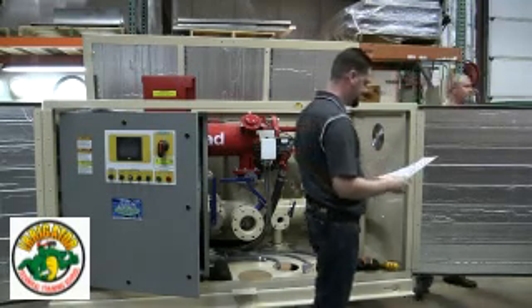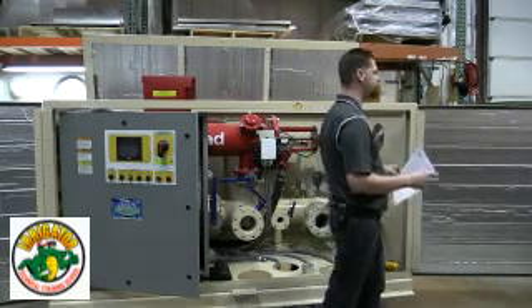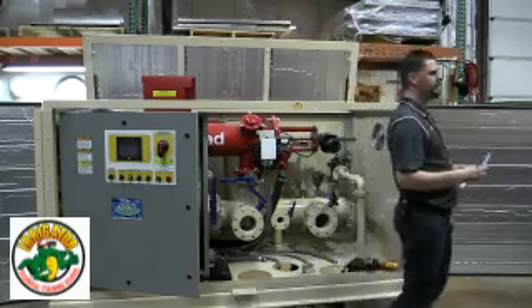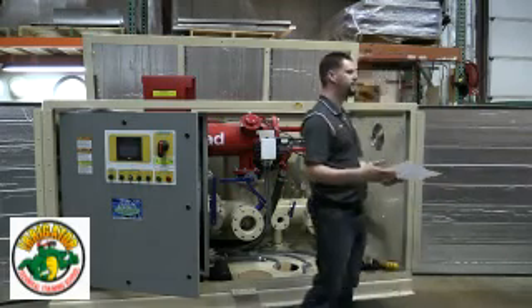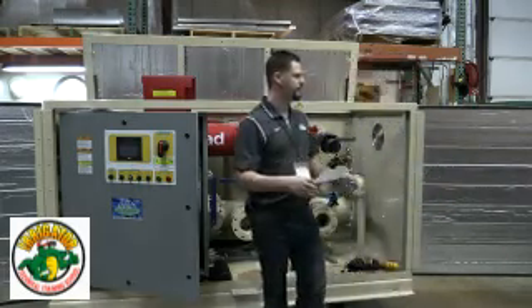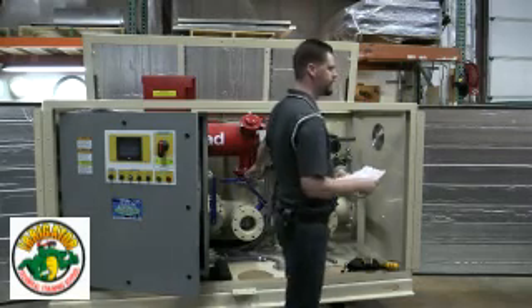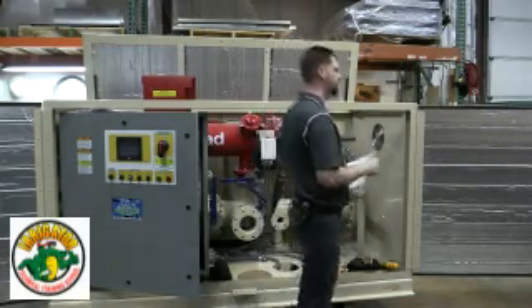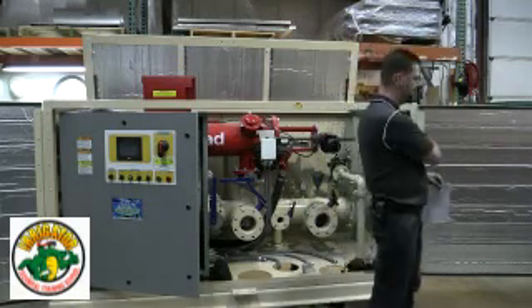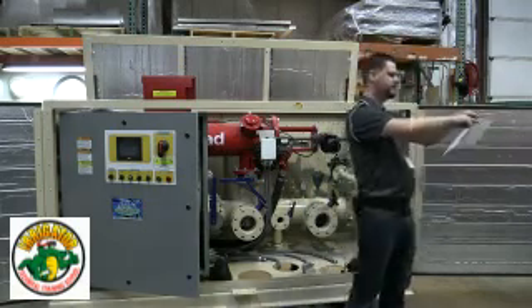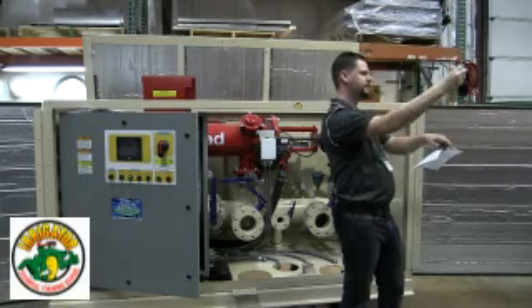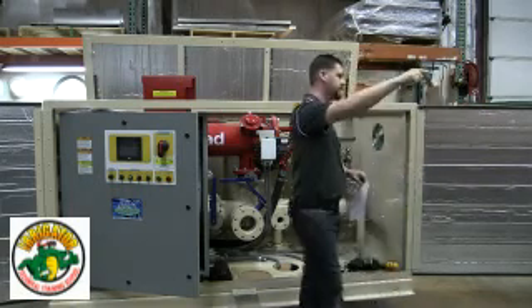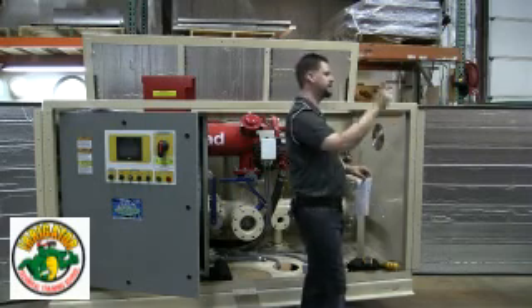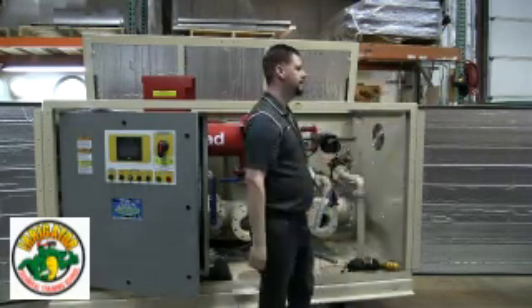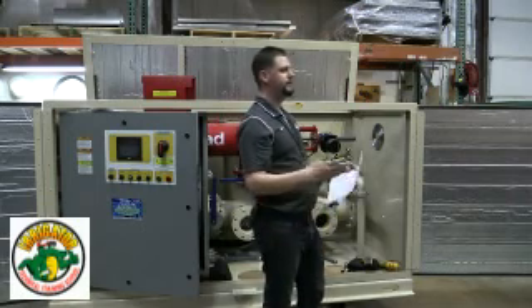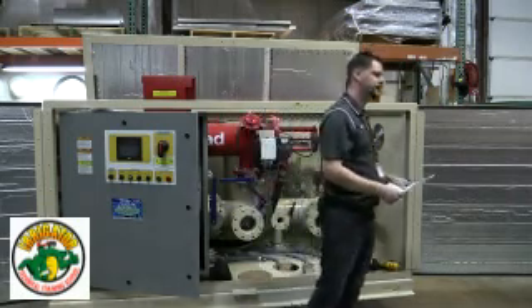We'll get to the filter here in a minute. The CW valve, or intake screen valve. CW valves, for those who don't know, are hydraulically powered. So we are supplying through a, like a sprinkler valve here. We're supplying water that's been filtered to this valve. There's these spray arms inside the valve with nozzles that are angled off so that the pressure going through them actually spins this whole armature around on a sealed bearing. So there's a lot of different possible places where that could fail.